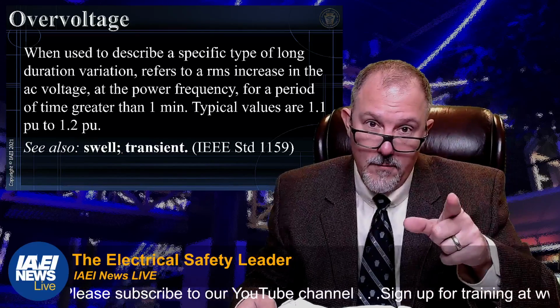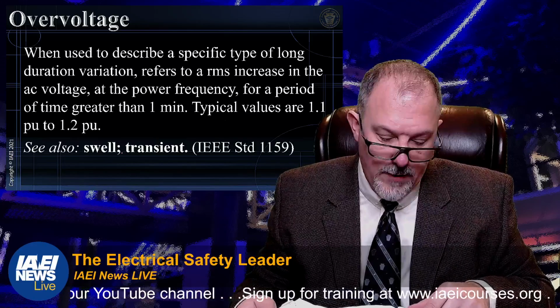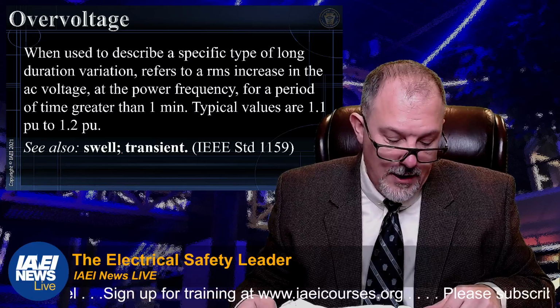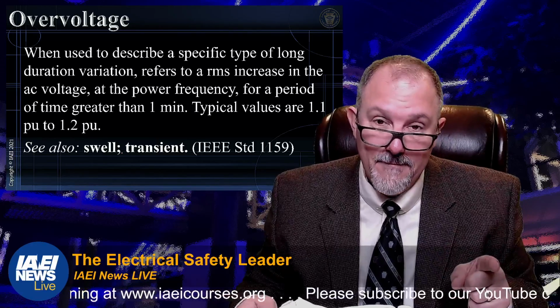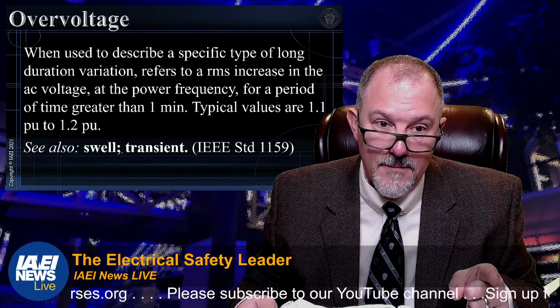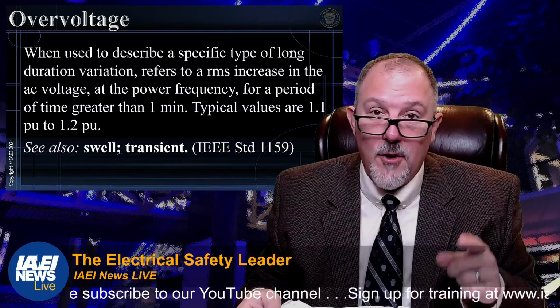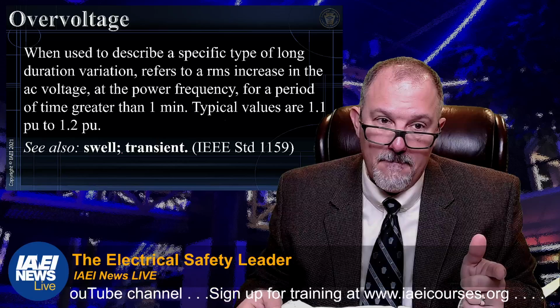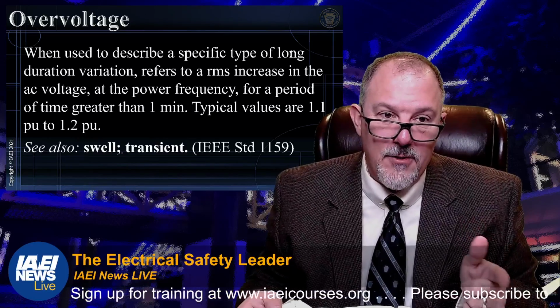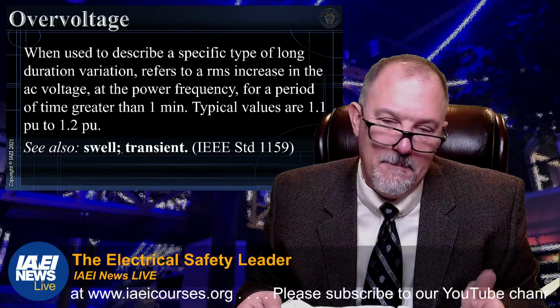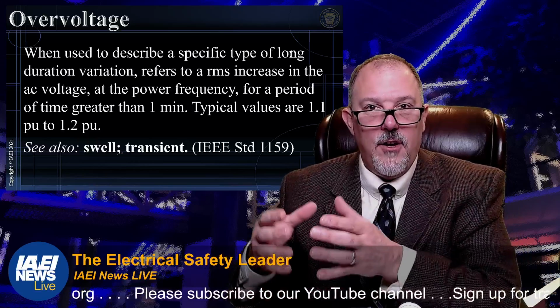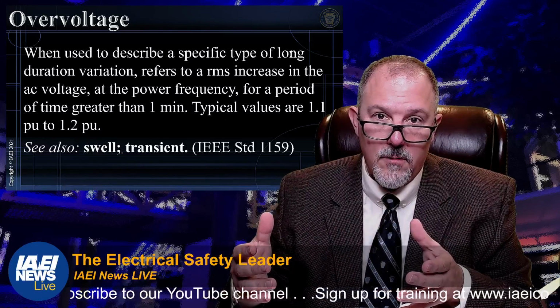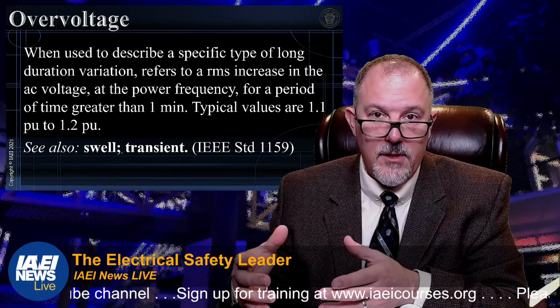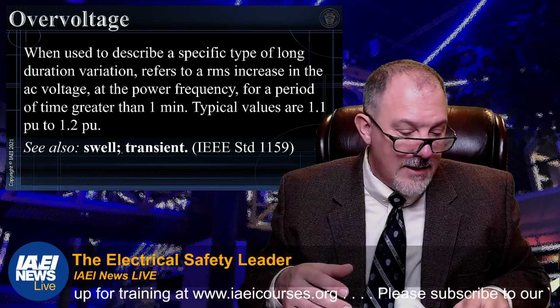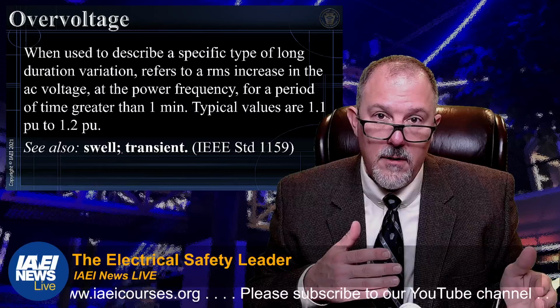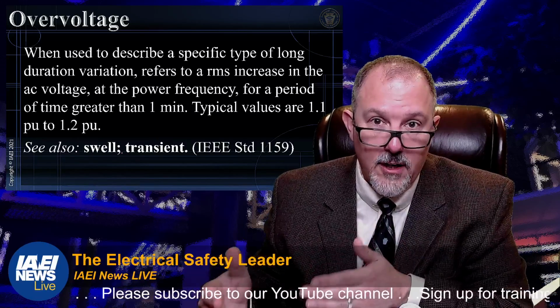Now, I could argue that an overvoltage is any voltage in excess of the rated voltage of equipment or the voltage ratings of conductors. And it may result from a voltage swell, a voltage transient, or RMS increases of voltage at the power frequency for a period of time greater than 1 minute, right? So I could say that a transient voltage event is an overvoltage, but an overvoltage is not always a transient voltage event. Just like I can say a short circuit is an overcurrent, but not all overcurrents are short circuit events.